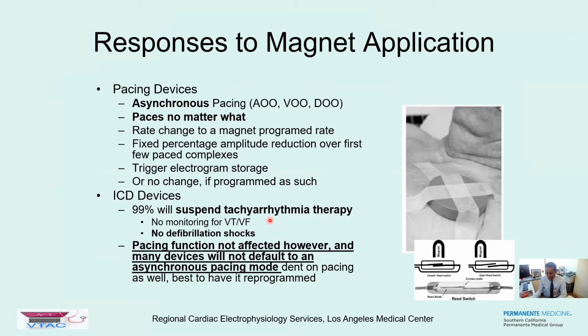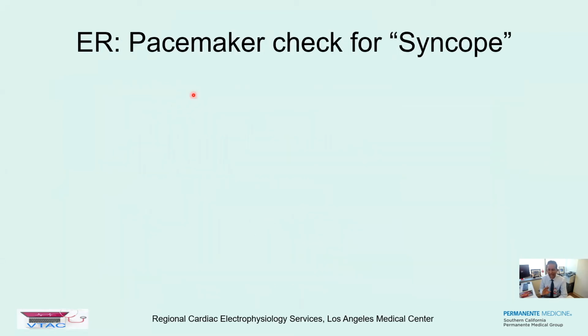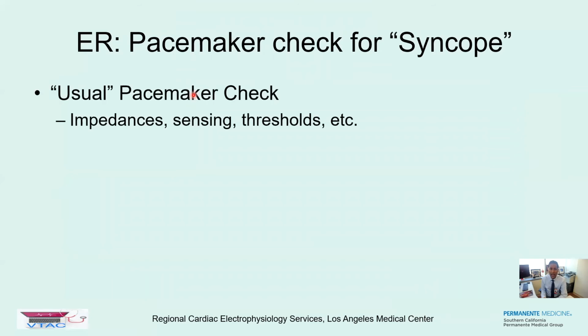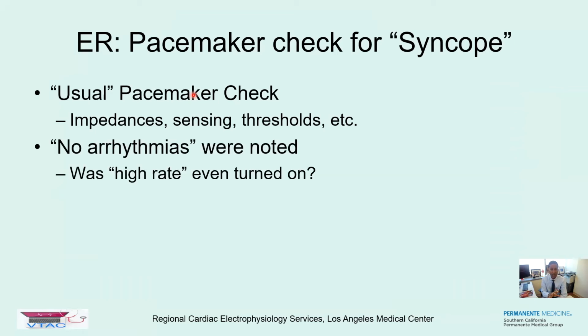Okay, how about this bonus question? What if a patient is passing out, they have a pacemaker and they're dependent, and they come into the ER for a check? You check their device and it's normal - the sensing, the thresholds - what should you check for? This is a common check for a CARDS fellow. Syncope with a brand new device, and they're in the ER and everything looks good. In fact, you even check for high rate arrhythmias, so that's another thing to do, which is basically make sure there wasn't a VT event. You make sure that it's actually turned on, you check that and it's fine.